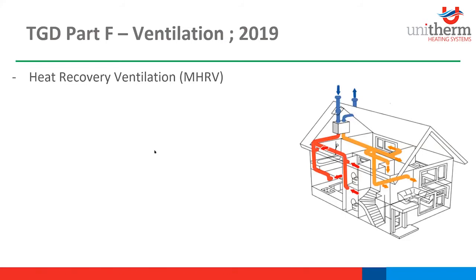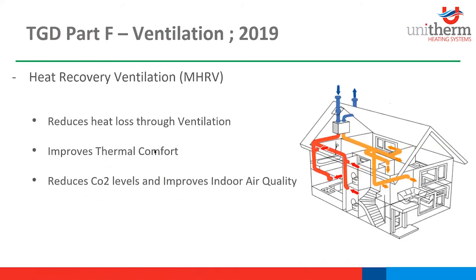So mechanical heat recovery ventilation reduces heat loss through ventilation. With ventilation losses being the biggest contributor to fabric heat loss, by making our dwelling airtight and using heat recovery ventilation, we're significantly improving energy performance. So the extract and supply ducts feed into a heat exchanger, and then without cross-contamination, they transfer heat from the warm air to the cold air. Usually the efficiency of this is between 85 and 90%.